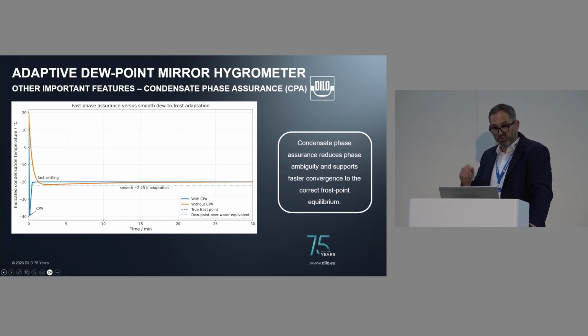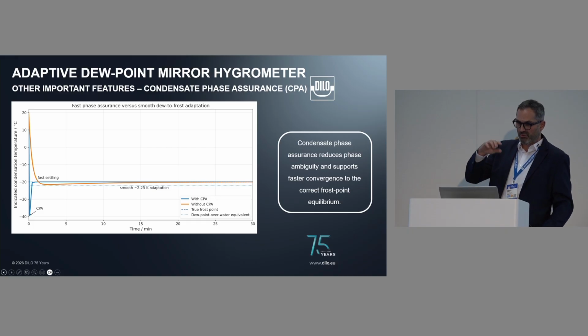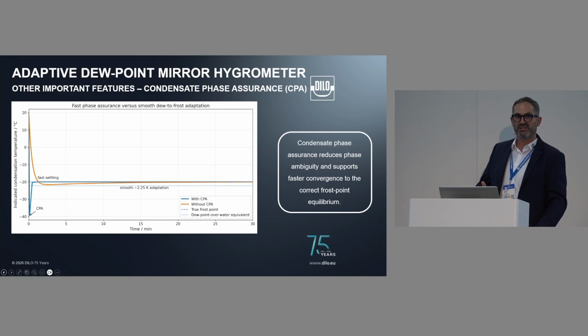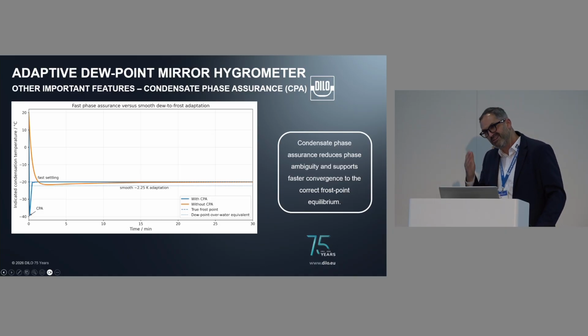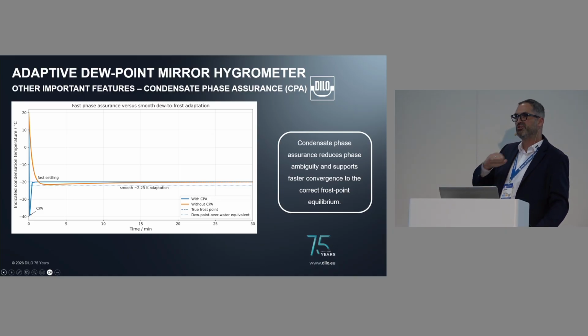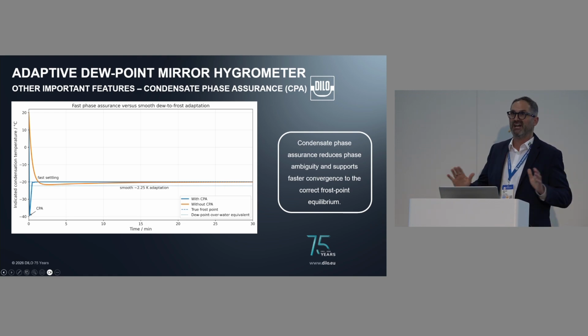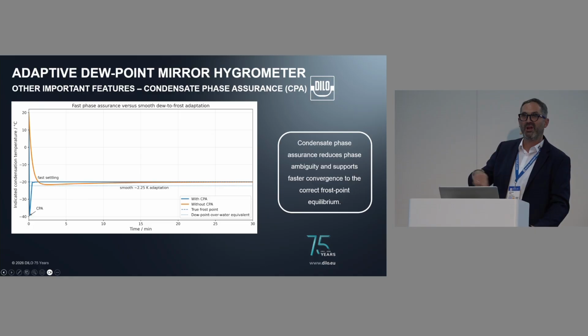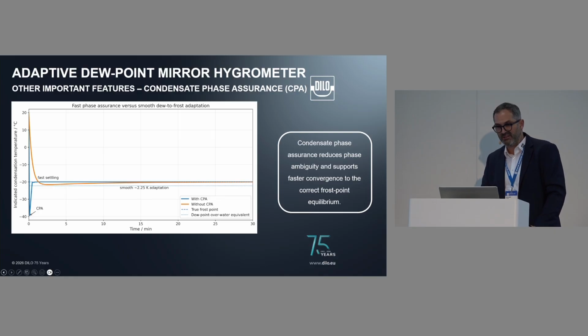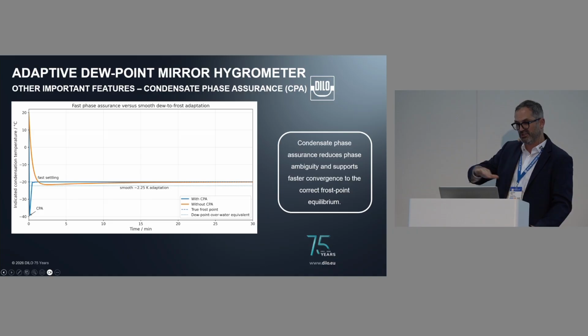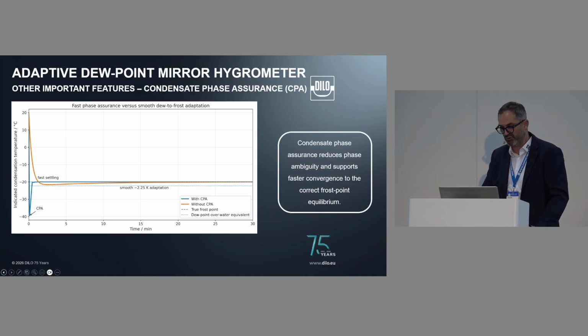So what we then do is, once we are below 0 degrees C, we cool the mirror to minus 40 degrees C, and then at minus 38 degrees C, this is a homogeneous freezing temperature, for example, and then we can make sure, okay, everything is ice on the mirror, and we have the correct value, and we know we measure the frost point then. If you won't have it, then you would have a very slow adaptation to the correct frost point value.